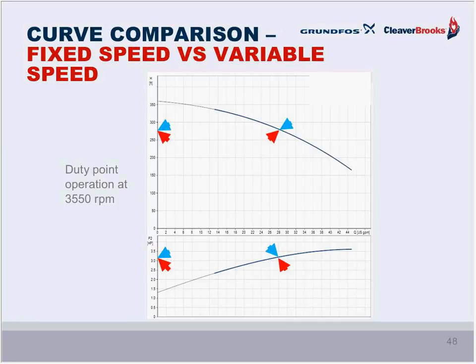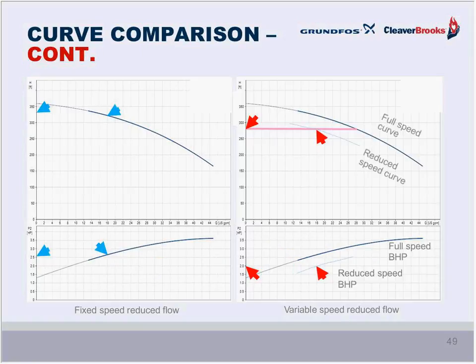Let's take a look at what's going on with the curves. Both of them, when we're calling for full steam, are calling for 28 gallons per minute at 272 feet, as you can see here. And both of them, if you look at the lower part of this curve, which is the horsepower curve, are calling for just about 3 horsepower. So what's the difference? Well, the difference is when the valve modulates closed, we have reduced flow. On the curve on the left, for a fixed speed pump, take a look at those blue arrows. As we work back to a lower flow, perhaps at 18 gallons a minute, you can see where the blue arrows are. With the fixed speed pump, we move up and to the left on that curve to about 325 feet. And that gives us a load of just under 2.4 brake horsepower when we adjust for specific gravity and some other factors.